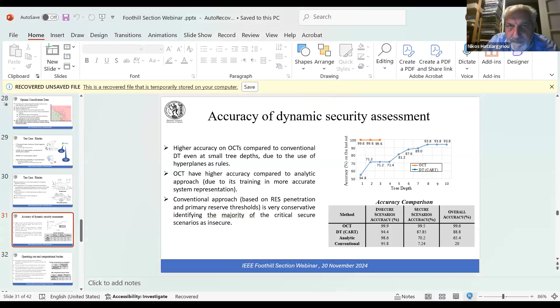If you look at the accuracy comparison between the optimal classification trees and other approaches like decision trees, on the overall accuracy on the right-hand side you see optimal classification trees have the best performance at 99.6%, decision trees 88.8%, analytic 65% (using the analytical relationship as described before), and conventional, using static limits, is clearly worse than all the other alternative technologies.